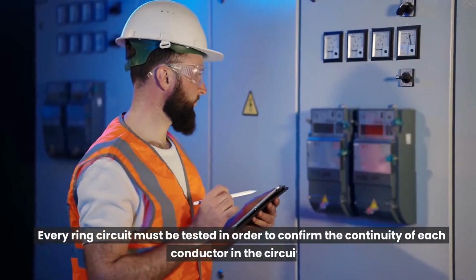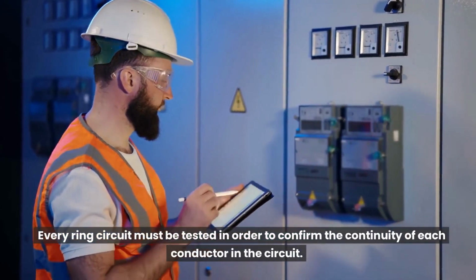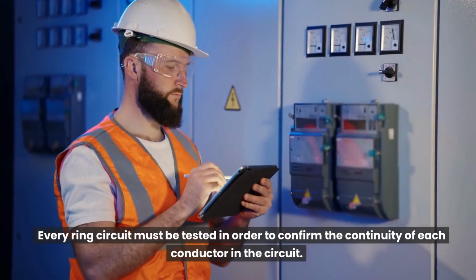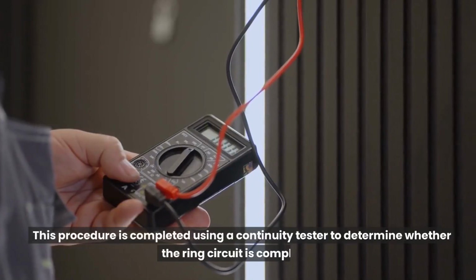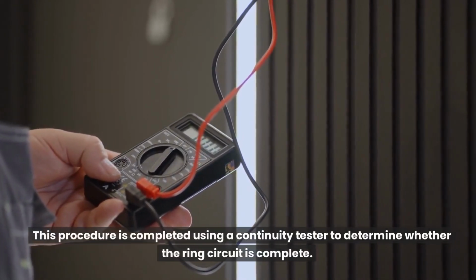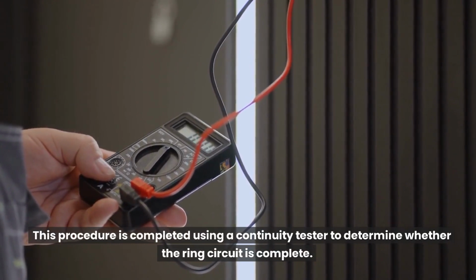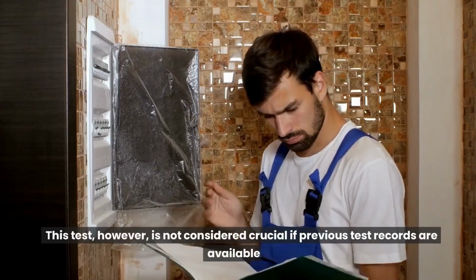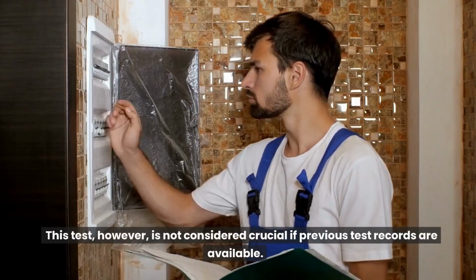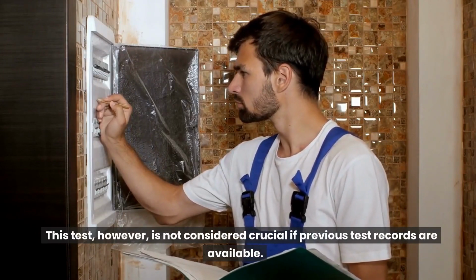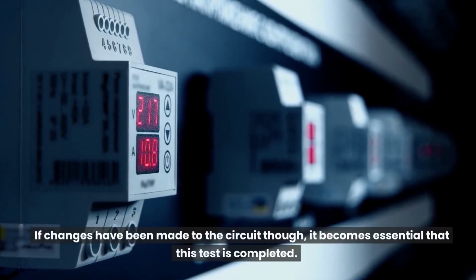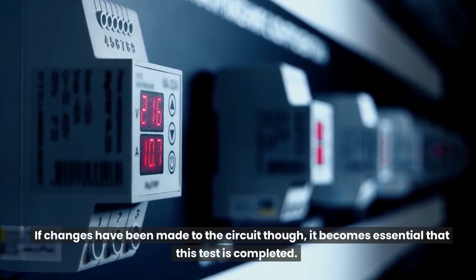Ring circuit testing. Every ring circuit must be tested in order to confirm the continuity of each conductor in the circuit. This procedure is completed using a continuity tester to determine whether the ring circuit is complete. This test, however, is not considered crucial if previous test records are available. If changes have been made to the circuit, though, it becomes essential that this test is completed.